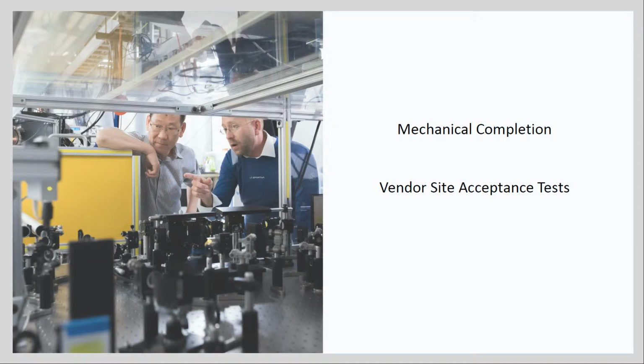So if the performance tests were performed on a pump, say the pump curve was measured in the factory, after shipping and installation, the vendor would want to confirm that their equipment is still intact and meets all technical requirements. The performance or the pump curve may be measured again on site to confirm that it still meets technical requirements. So with those two sets of results from the factory and from on-site testing, you get a pretty good idea and can compare to see if there's any differences or any damage or upset to the piece of equipment from the factory to on-site.